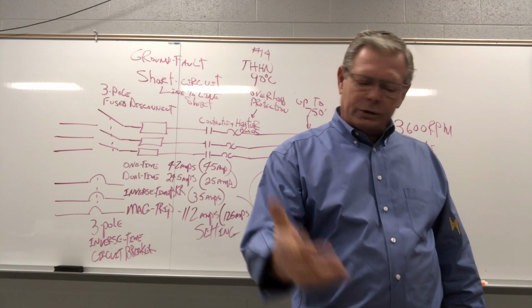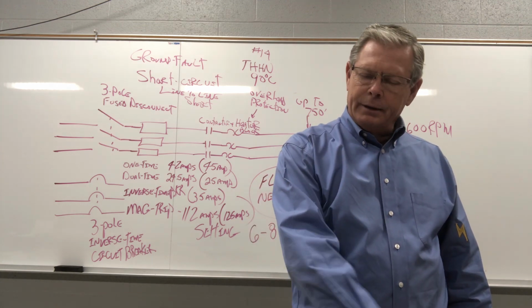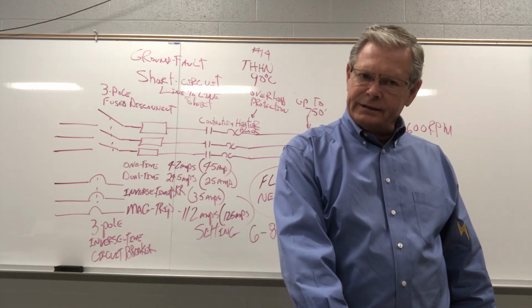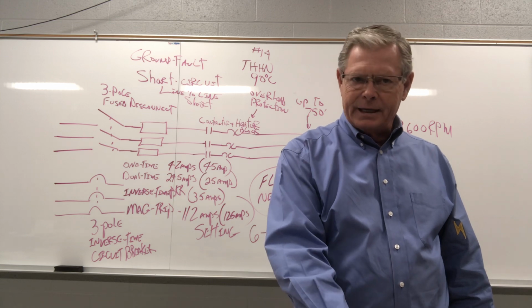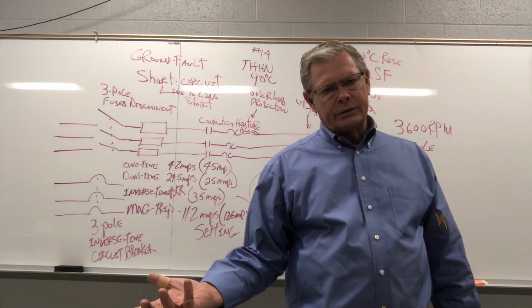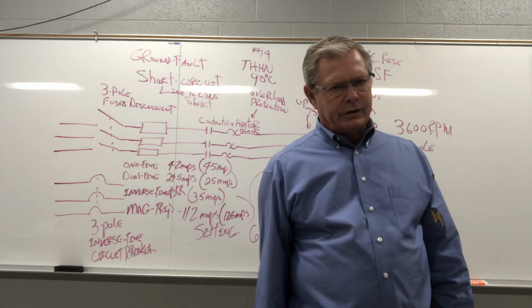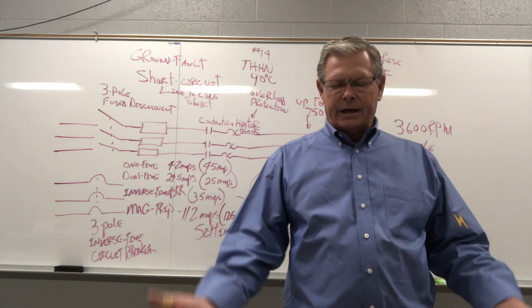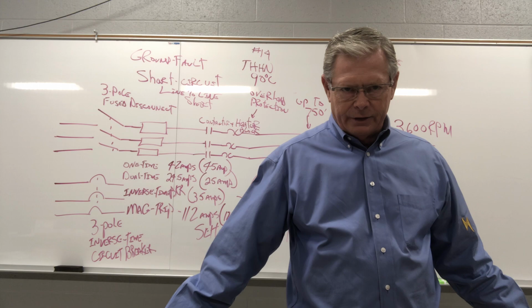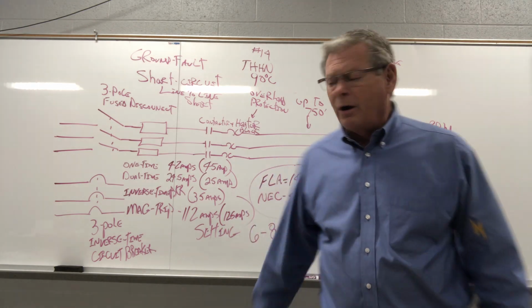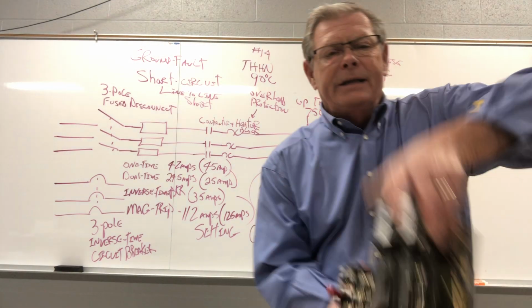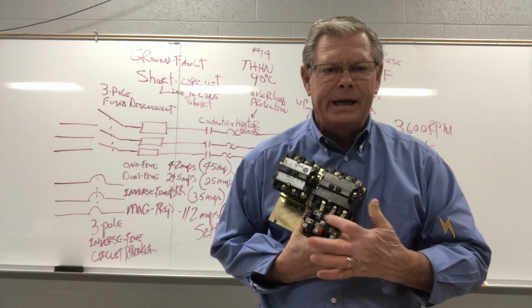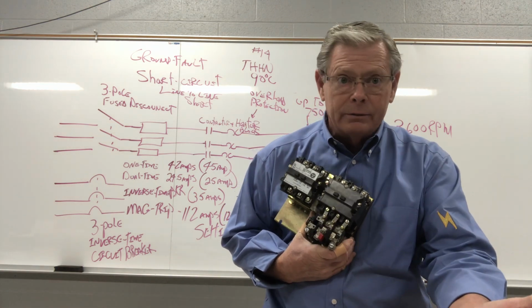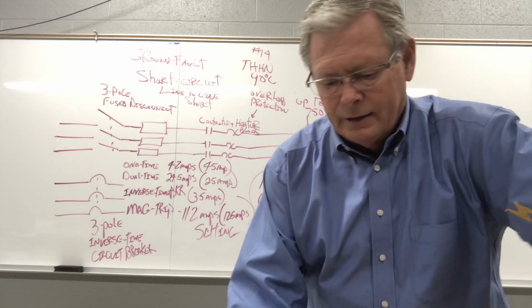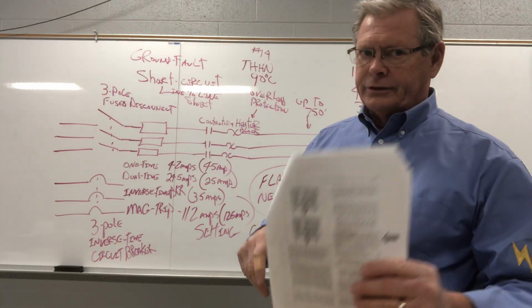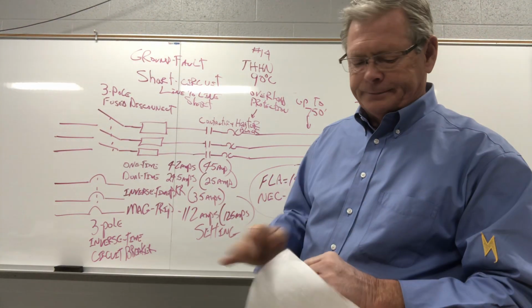Well, a 15 horse is not going to bolt up to the same bolt hole patterns as a 10. So you got to change out the base. Then it's not going to bolt up to the same gearbox. Now you got to get a new gearbox. Then you got to take a jackhammer out the base and all that other stuff. But if we know this, all you got to do is calculate, change out 3 heaters, and you go from 0 to hero. Okay, so it pays to understand motor circuits.